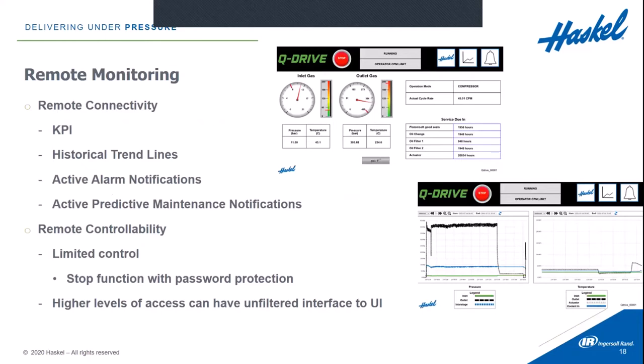Built into every Q-Drive, you have the ability for remote monitoring. If you have a provided internet connection or some sort of cell connection to the drive, you can connect to the drive from anywhere and pull up your remote dashboard. On the remote dashboard, you'll be able to observe all of your system pressures and temperatures, modes of operation, and service counters, so you can know when service is due on the drive. On your remote monitoring interface, you'll be able to put in your cell phone number or email so your service technician can be notified by email automatically when service thresholds are hit. Some of those thresholds are already predefined; others change predictably depending on the amount of usage and how hard you're running the drive.